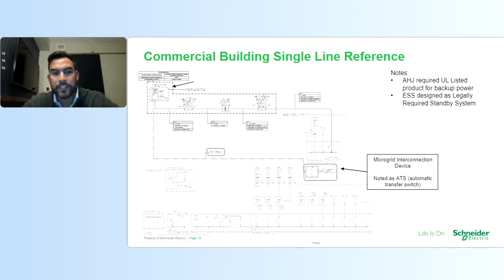We actually ripped and replaced the transfer switch with the automatic interconnection switch. Same dimensions here. This was a 600 amp product. And this enabled the energy storage system to really save time on deployment. Given the UL listing, a lot of these, depending on the AHJ, require third-party testing. And if you don't have a UL listing, it requires you to go through some type of third-party agency and actually test that this device is intended to operate as an automatic interconnection switch, which in this case, we had these products readily available in stock. We were quickly able to ship out and bypass that third-party testing.